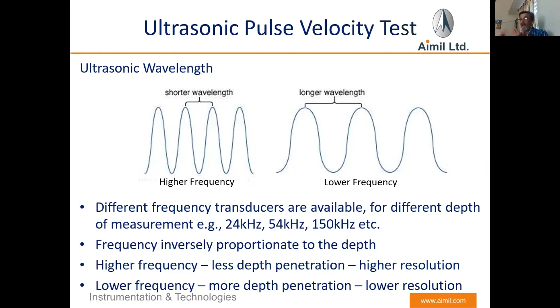It is just trial and error; you have to test for a particular site, and you can arrive at a conclusion for that particular site only. So, this is the case: high frequency gives less depth penetration but high resolution, while lower frequency gives more depth penetration but very low resolution. So there are different testing methods also.